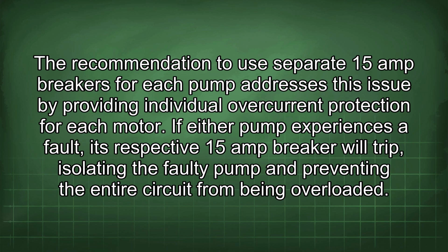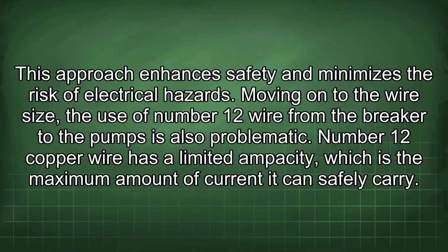The recommendation to use separate 15 amp breakers for each pump addresses this issue by providing individual overcurrent protection for each motor. If either pump experiences a fault, its respective 15 amp breaker will trip, isolating the faulty pump and preventing the entire circuit from being overloaded. This approach enhances safety and minimizes the risk of electrical hazards.